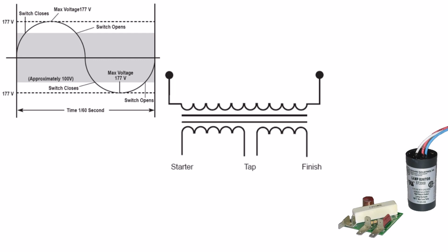Let's talk a bit more about the ballast, because it's a real workhorse of a high-pressure sodium luminaire. During startup, the ballast helps generate that high voltage spark. But once a lamp is running, its job shifts. It regulates voltage and current so the lamp doesn't overheat or burn out.